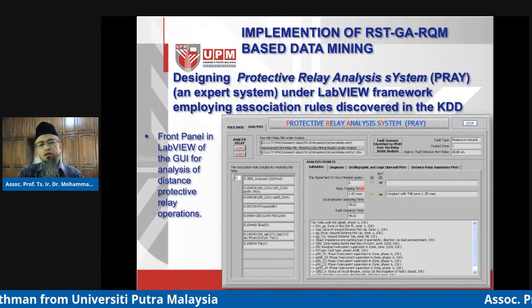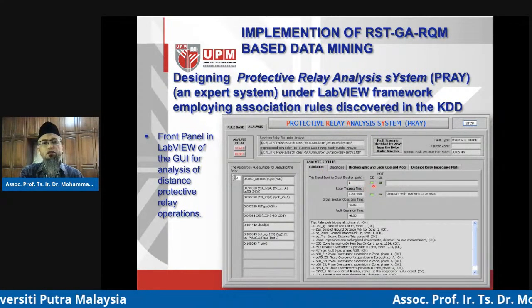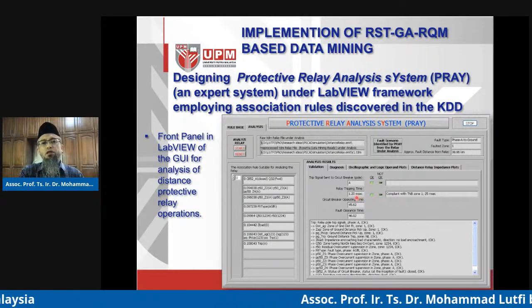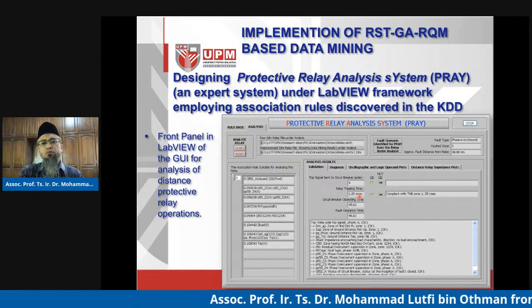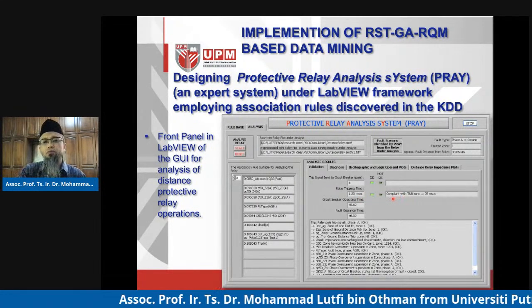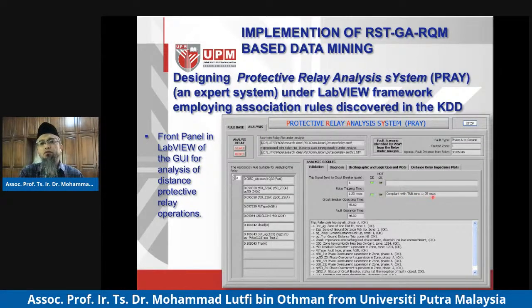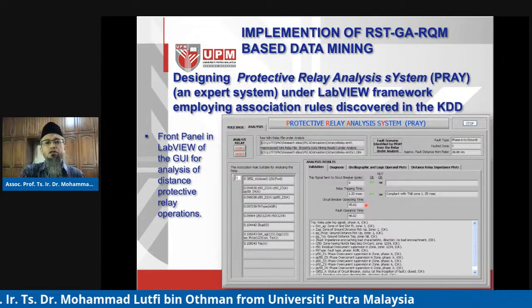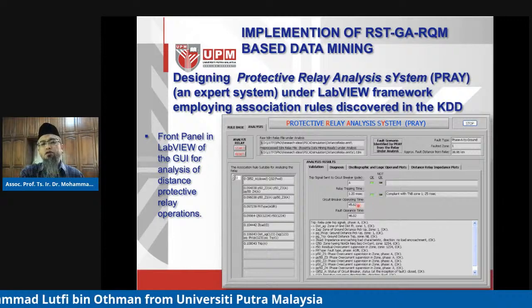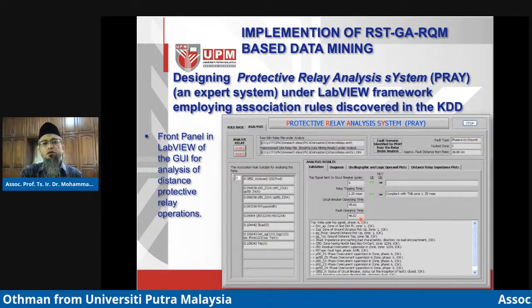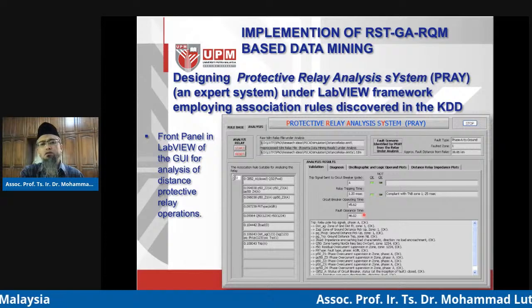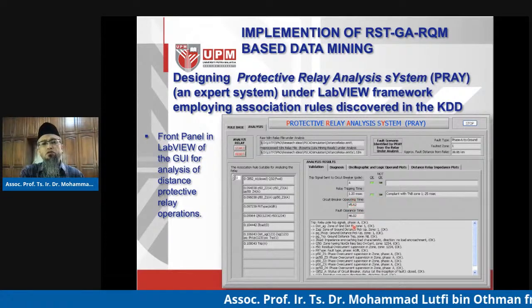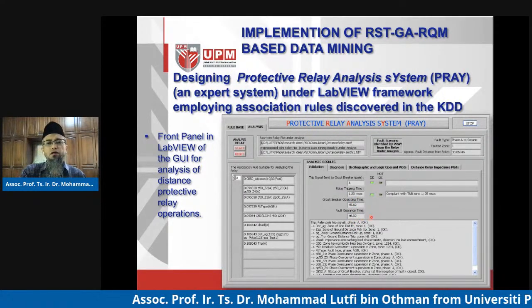So it's a validation field. Breaker A has tripped accordingly, correctly. The relay has actually tripped in 1.2 milliseconds, and it's very much compliant with the required TMB time of 25 milliseconds. The circuit breaker operating time is 46 milliseconds, and all in all, the overall time taken to finally clear the fault is 47 milliseconds.